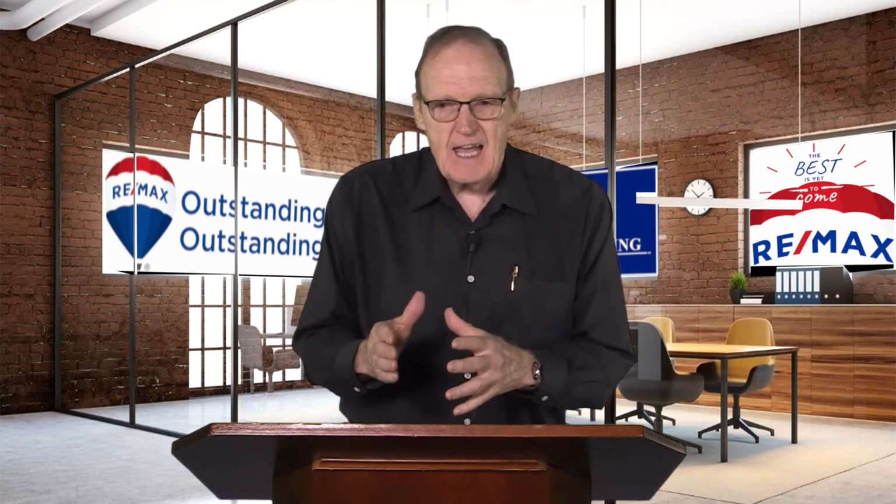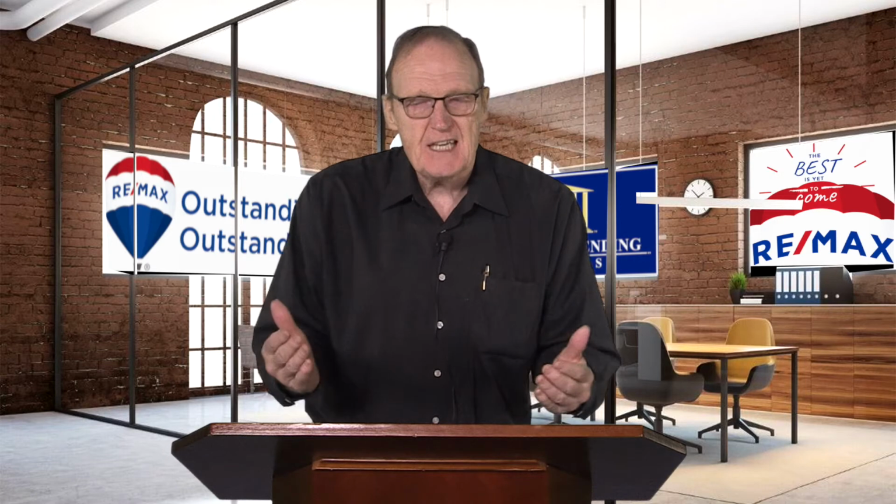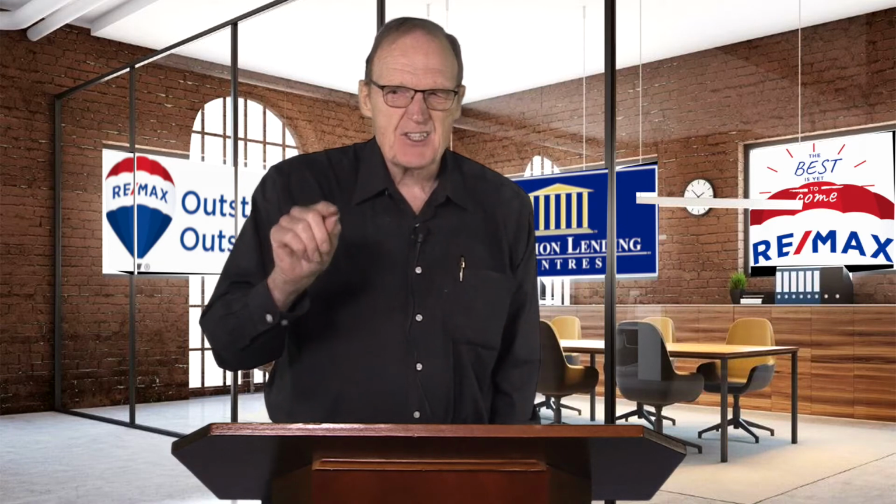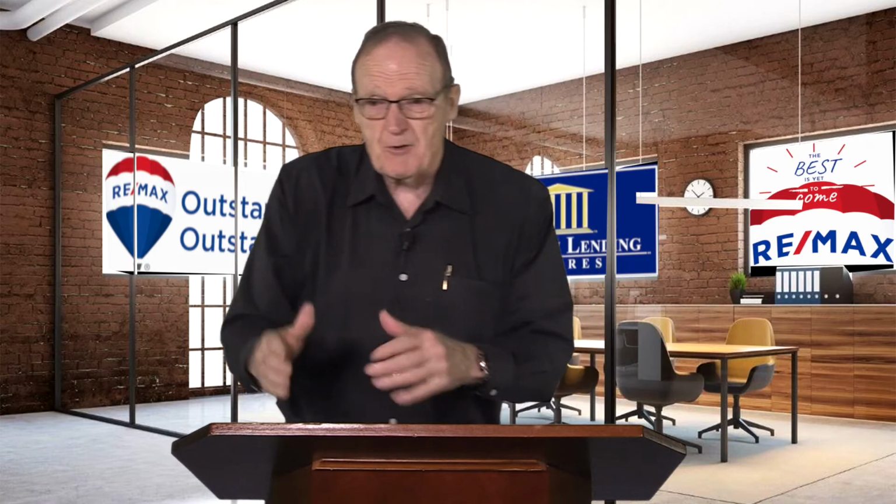And that is the issue that if a fire breaks out in a unit of a multi-unit building, how long will that fire be contained in that unit before it spreads to an adjacent unit? And that's a really important factor. It's one of the most important factors. One of the things that they look at is the drywall or the plaster or whatever the surface of the walls. Is it fire rated to 30 minutes, that it will take 30 minutes to burn through to the next unit or up to the unit above or down below? And so we want fire rated drywall or plaster that will withstand that.